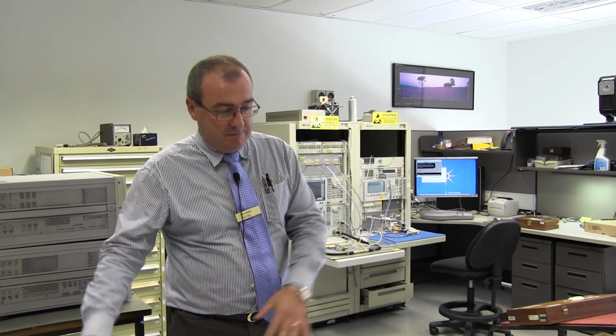As in physical standards, physical dimensions standards, weights and measures, the hardness. They're probably more impacted by humidity than we are. We are more concerned with things being too dry than being too wet, because it gives us an ESD problem, electrostatic discharge, if it's too dry. Within our laboratory, if you look at the floor, it's a particular floor. It's an ESD floor that's bonded properly and allows us to maintain an ESD safe environment. The average time when you pull your jumper off and you feel a zap, you're discharging about 3,000 volts worth of potential. So ESD is important to us, but our environment in our standards lab is very tight temperature-wise because of the precision required with the standards we're working with.